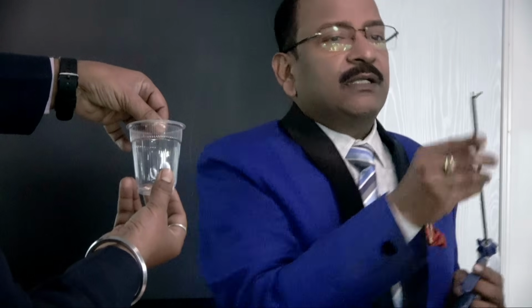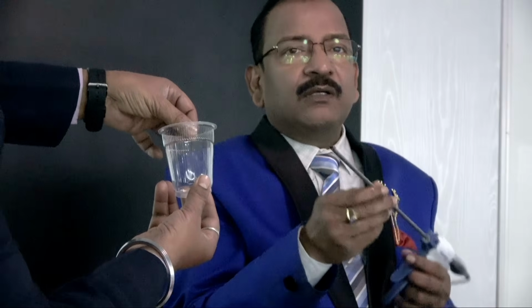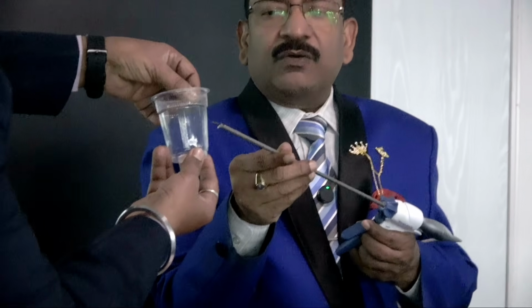And why was my finger not getting damaged? Because I was holding the Teflon jaw. And this Teflon jaw is of no use. This moving jaw is called the Teflon jaw. The moving jaw has only one purpose, to bring the tissue near the vibrating jaw. That's all. And you can use it even for, suppose you want to do colpotomy, then you don't have to close the jaw. And only by the open jaw you can do colpotomy.